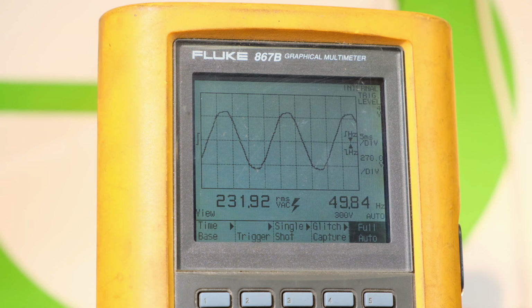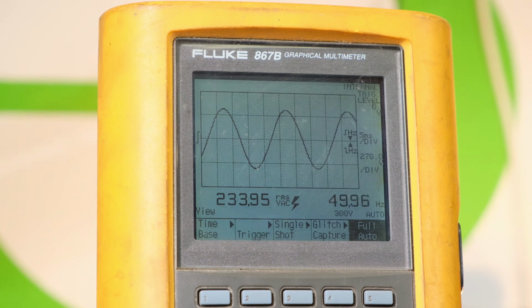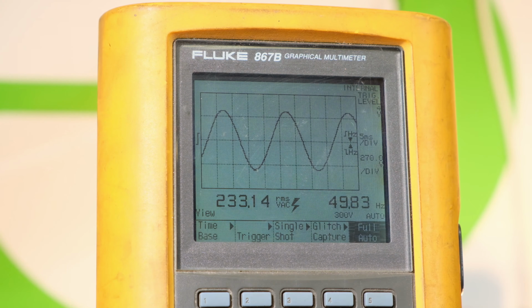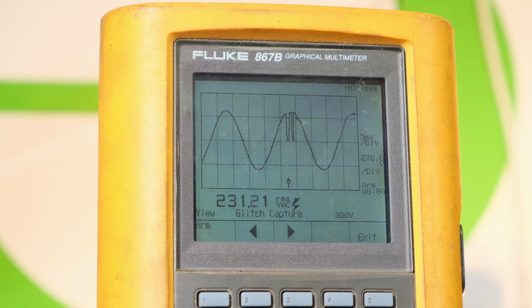The mains is now plugged in. There's the voltage at 231, and the frequency at 49.85. Now I'll unplug the mains and look at that waveform. There was a little bit of noise on the waveform before it switched back on. Understandably, there's some noise when the unit goes from mains to inverter and back.